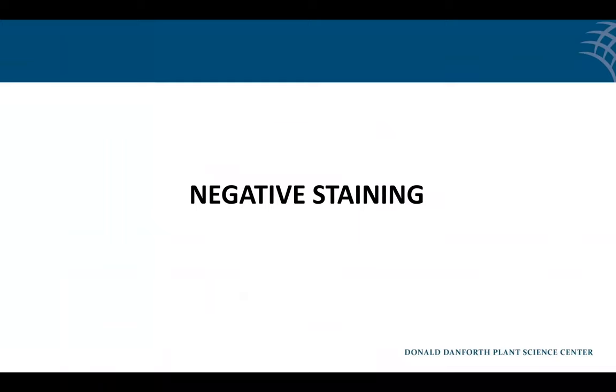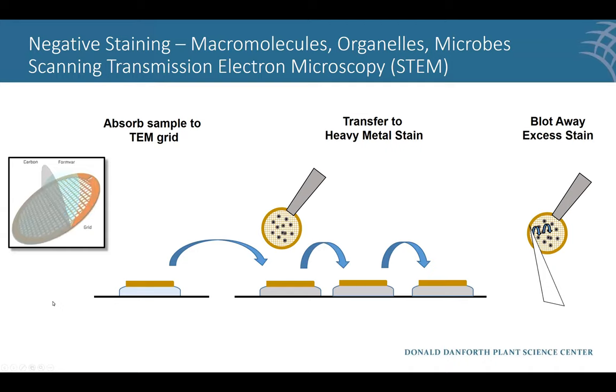Another technique that can be used on an SEM is called negative staining. This is actually one of the easiest techniques — if I were to pick anything to teach a new user on an SEM, it would be negative staining if you have a STEM detector. Normally we use grids about three millimeters in diameter with a thin electron-transparent polymer coating called Formvar — basically a plastic — with a thin carbon layer on top for stability. You place these grids on parafilm or dental wax, put a drop of whatever you want to absorb — commonly macromolecules, organelles, or microbes like viruses — and let it absorb for a few seconds to minutes.